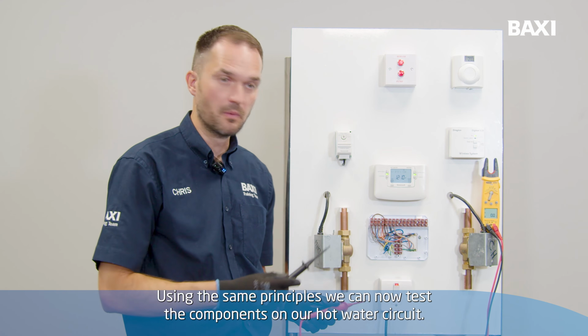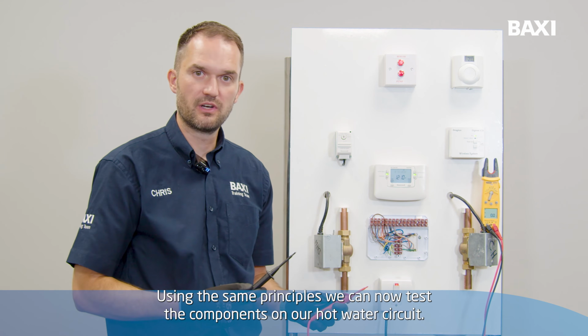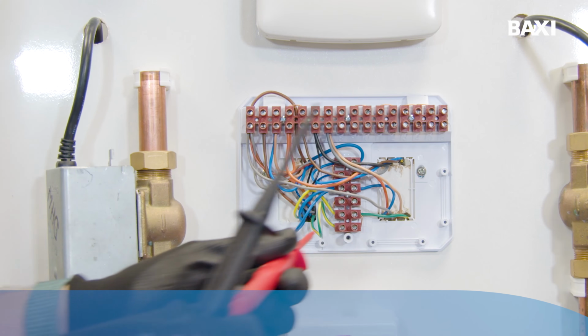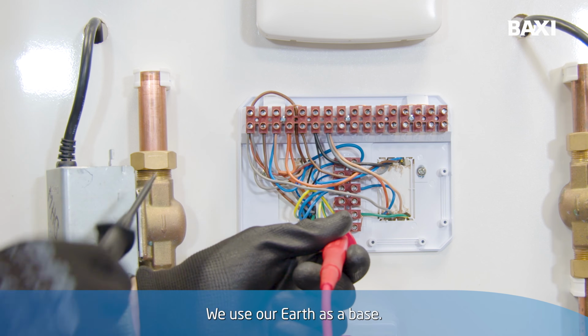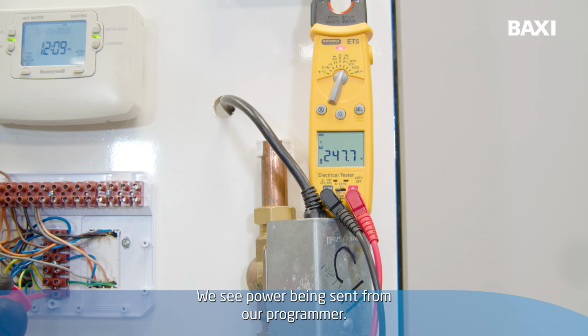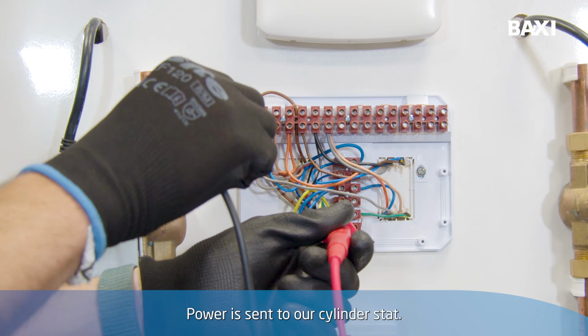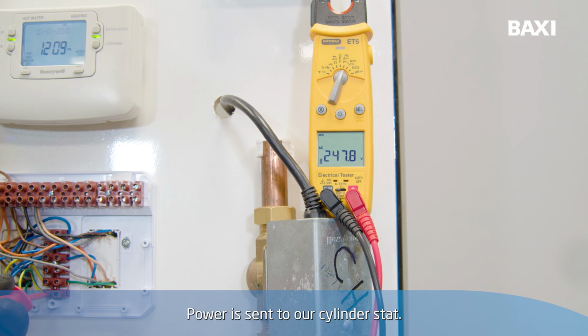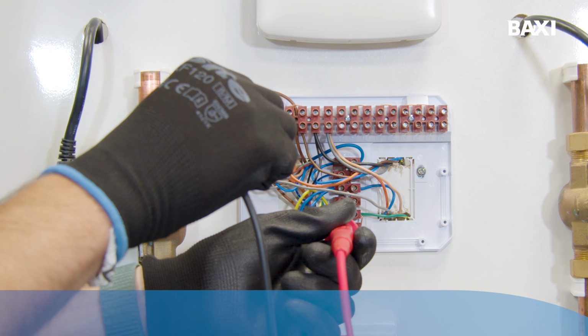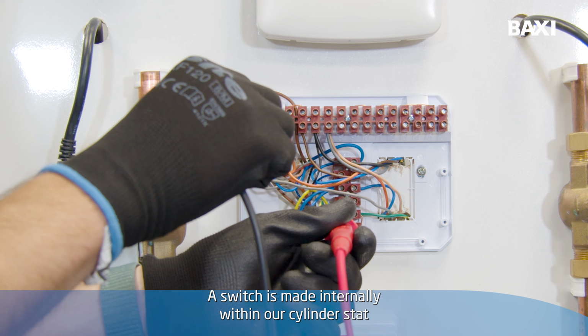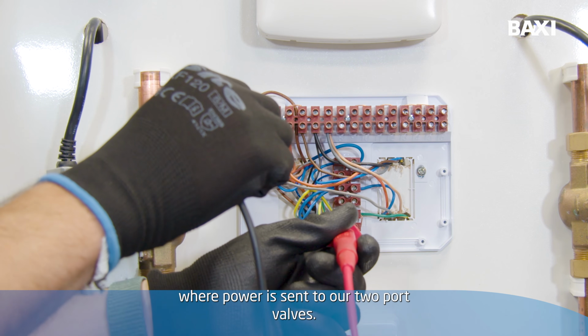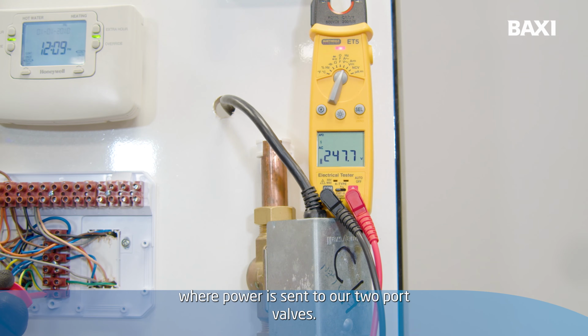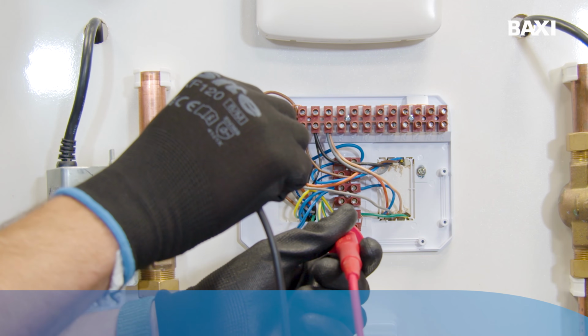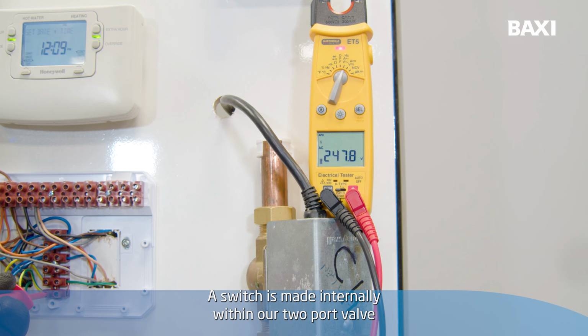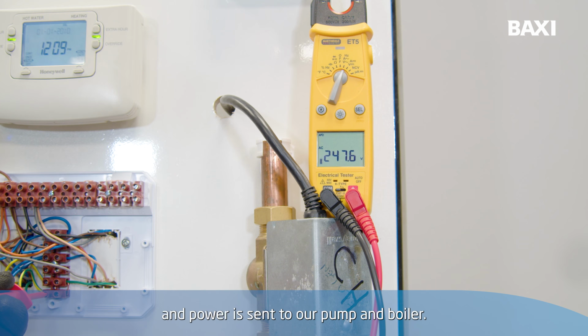Using the same principles, we can now test the components on our hot water circuit. We use our earth as a base. We see power being sent from our programmer. Power is sent to our cylinder stat. A switch is made internally within our cylinder stat, where power is sent to our 2-port valve. A switch is made internally within our 2-port valve, and power is sent to our pump and boiler.